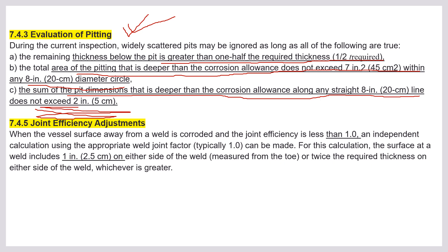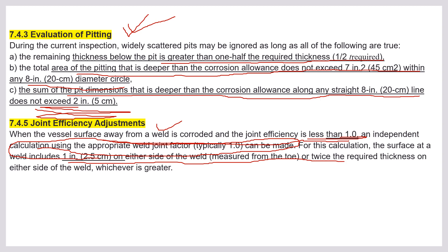Joint efficiency adjustment is also a common exam question. When the vessel surface away from the weld is corroded and the joint efficiency is less than 1.0, an independent calculation using the appropriate weld joint efficiency can be made. For this calculation, the surface at the weld includes 1 inch on either side of the weld, or twice the required thickness on either side of the weld, whichever is greater. This close-book question has appeared in exams many times.